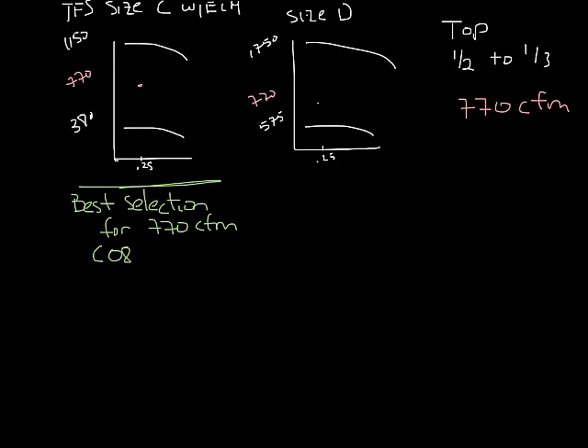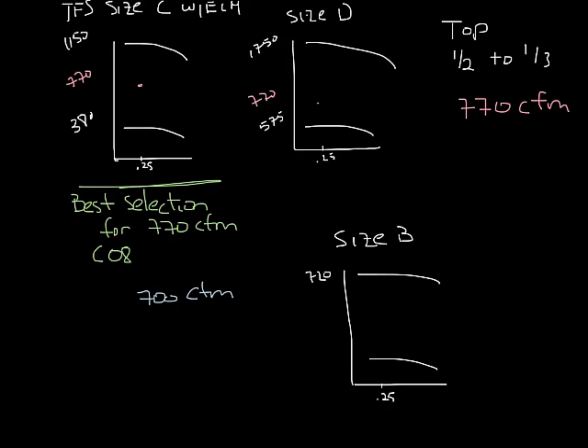Now if you needed 700 CFM, there would actually be three possible unit casing sizes that would work, because the size B TFS with the ECM motor has a fan curve that has a maximum at 720 CFM at 0.25 inches.